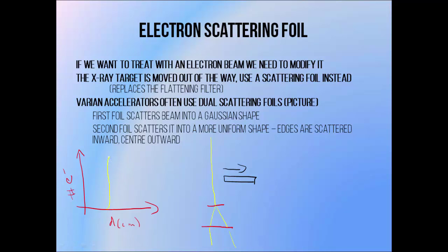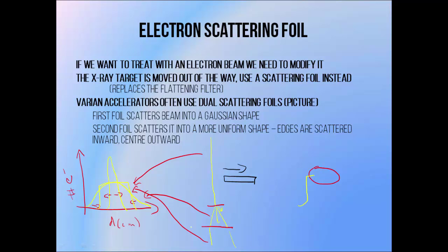If you look at the profile across the pencil beam — the number of electrons versus distance across the beam — it is quite narrow. Hitting the first scattering foil spreads it out significantly into a Gaussian shape or normal distribution, because electrons are more likely to be scattered a little bit than a lot. The job of the second foil is to generate a more uniform profile by scattering electrons from the edges into the centre and from the centre towards the edges. We like to have flat beams because it means we can give a fairly high and uniform dose to a target, whereas a Gaussian shaped beam would require giving a lot of extra dose to the surrounding tissue to achieve the same minimum dose inside the target.